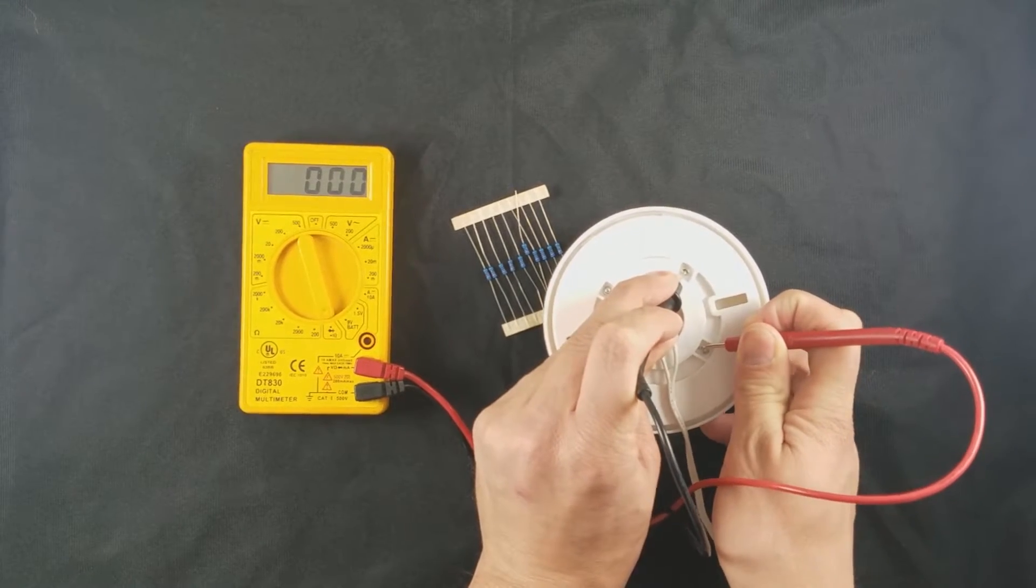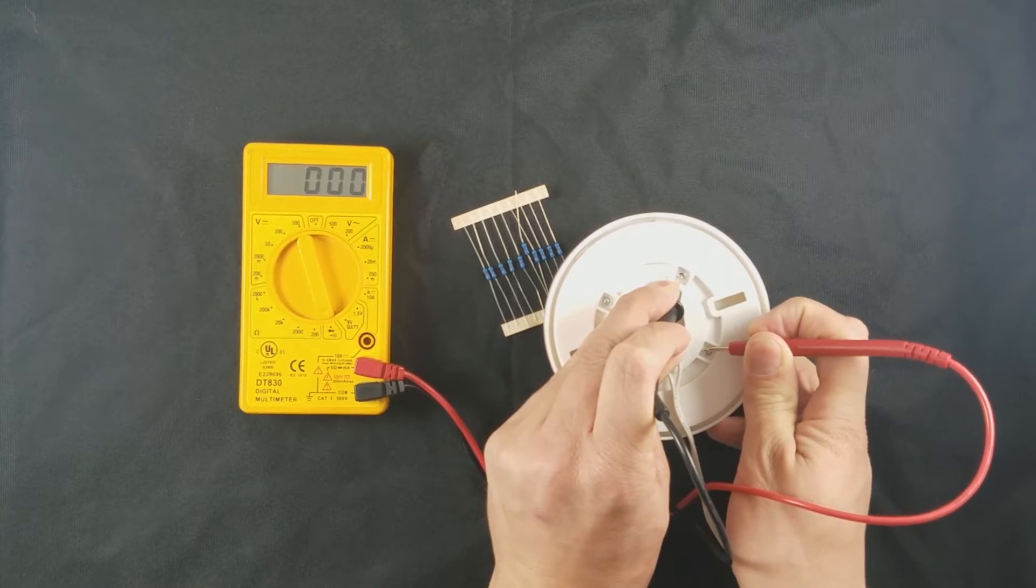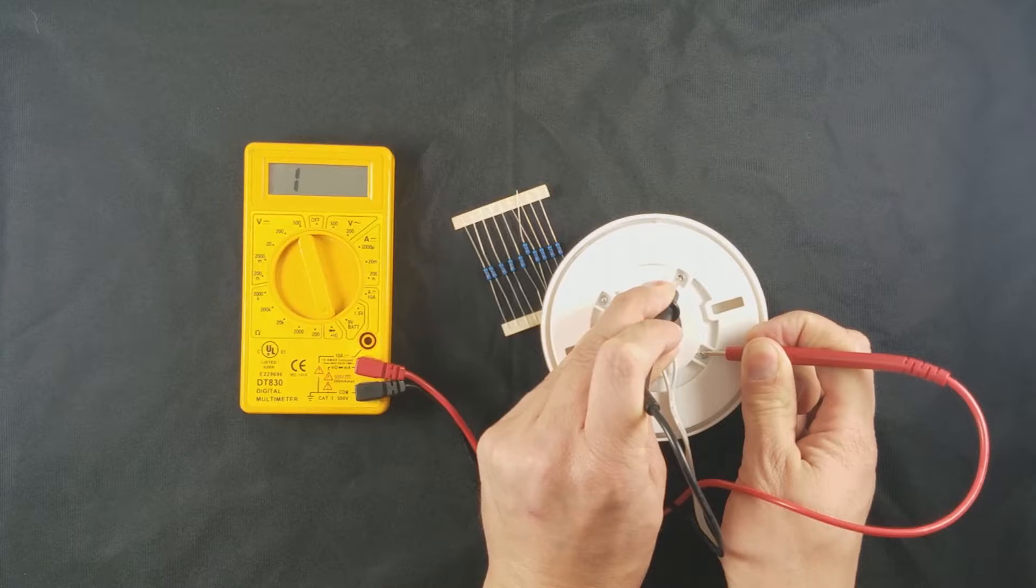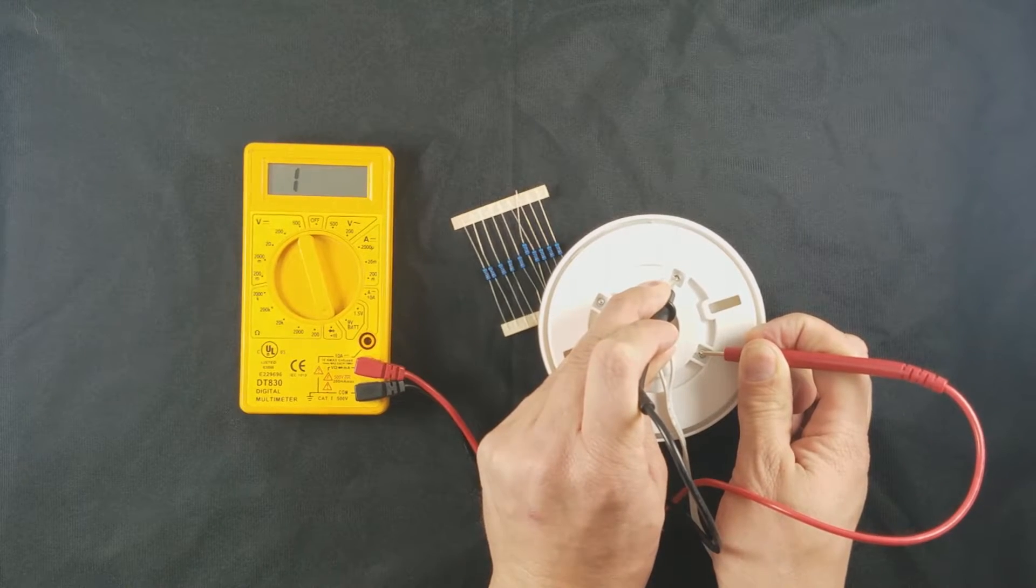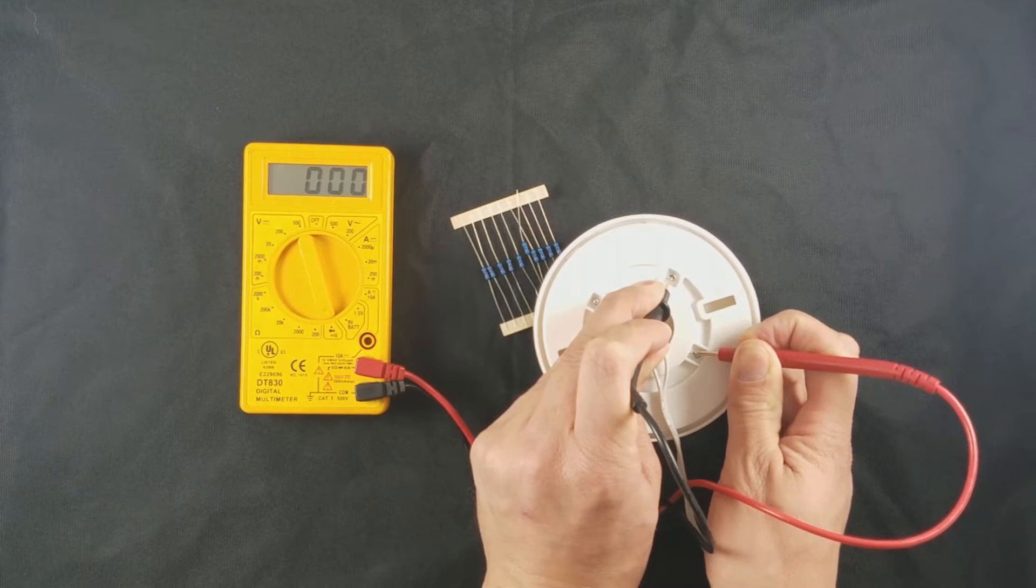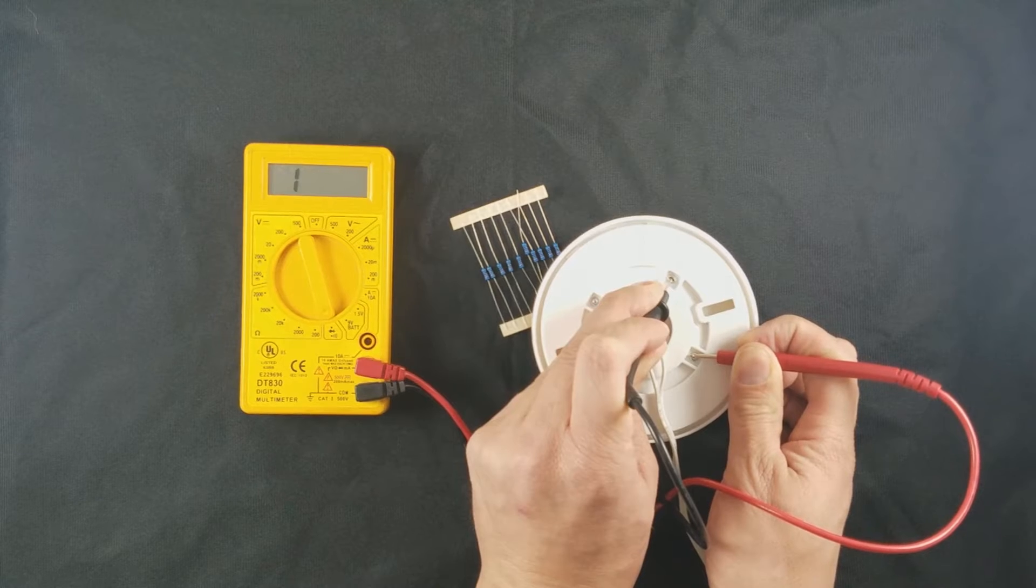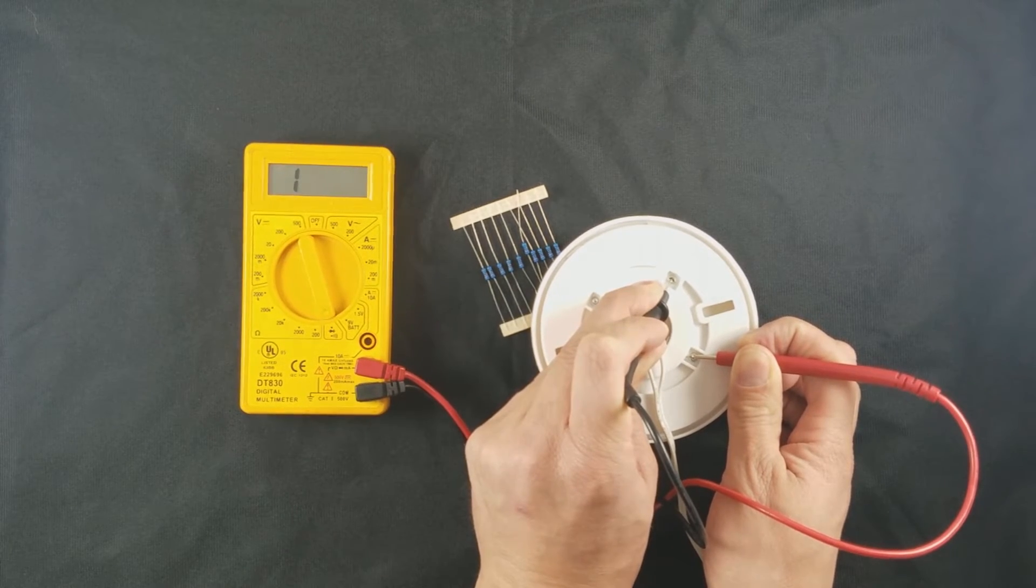Let me show you this again. I'm going to press the test button underneath. You can see while it's in alarm, it goes to open. Right now it's open, and when the alarm stops, it goes back to closed. That's how you test to make sure the smoke detector is working properly.